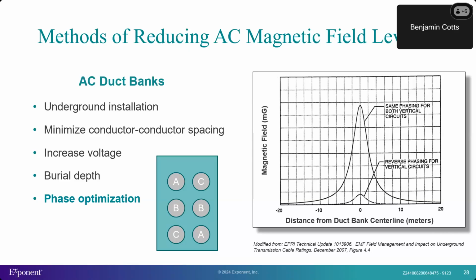If we look at the graph on the right, this shows field strength as a function of distance from the center line. The larger graph shows a configuration with the same phasing for both circuits on each side — an ABC, ABC configuration. The lower graph shows a duct bank identical in every way, except instead of ABC on both sides, it's ABC on one side and CBA on the other. This method of phase optimization can be very effective in reducing magnetic field levels.